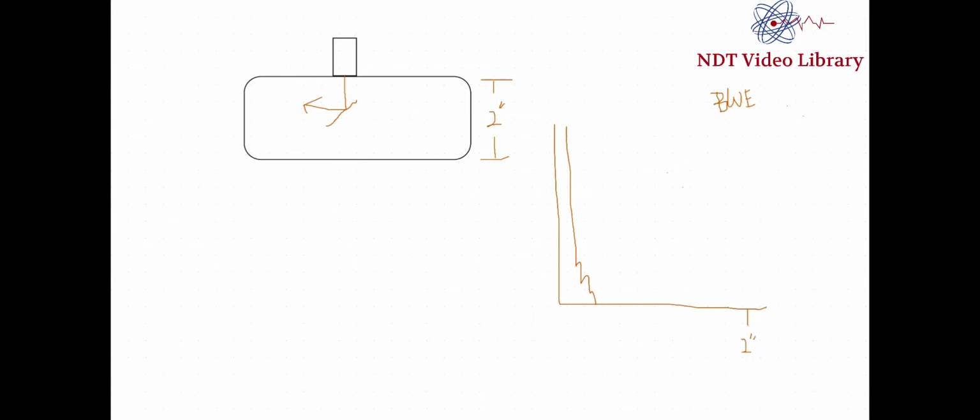Yeah, that's also possible that your cable has stopped working. So in that case, you just bring the transducer back to the place where you used to get signal before. And now if you still don't get the signal, that means your cable has gone bad or there's a loose connection. You need to tighten it, right? So if you get the signal again and you're still not getting the signal over here even after adding couplant, then there is a possibility that there is a defect that is at an angle that is diverting your sound.